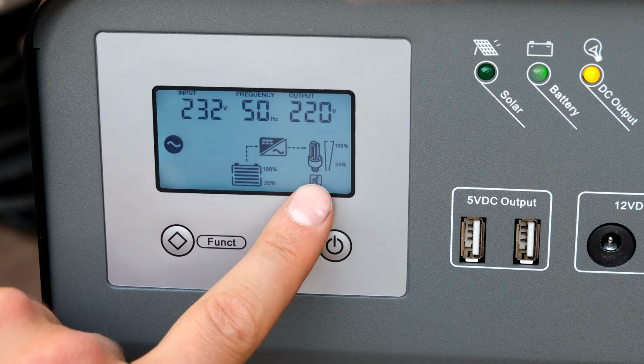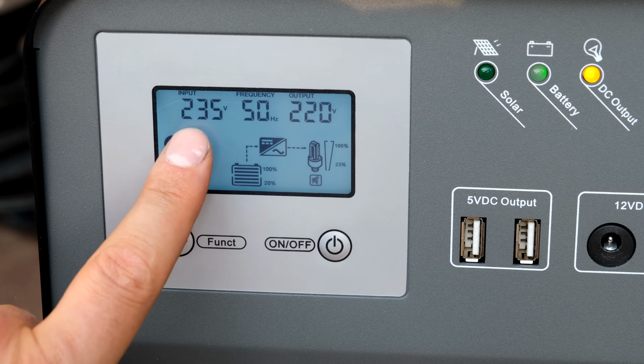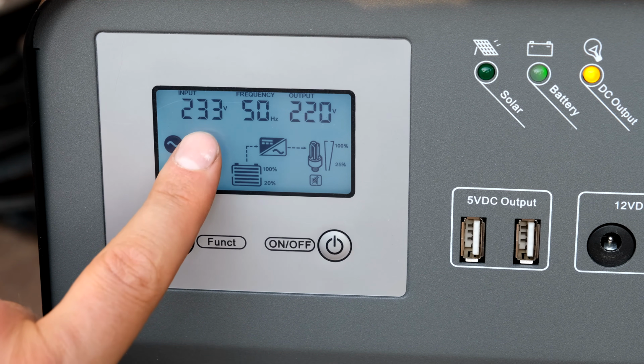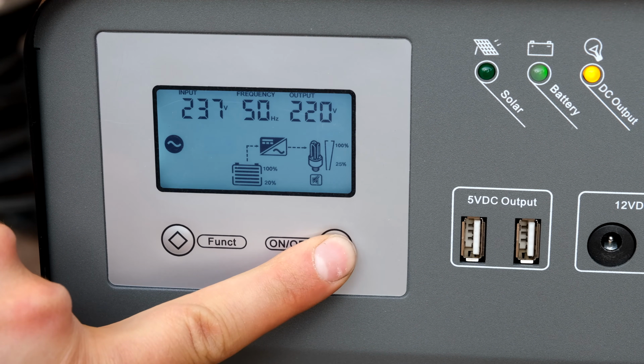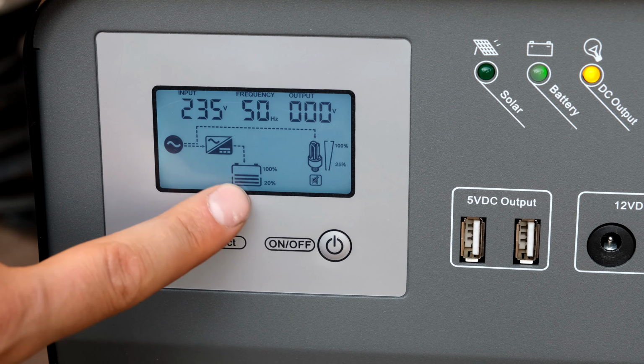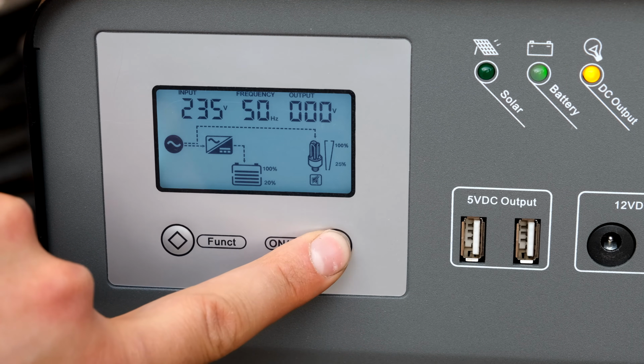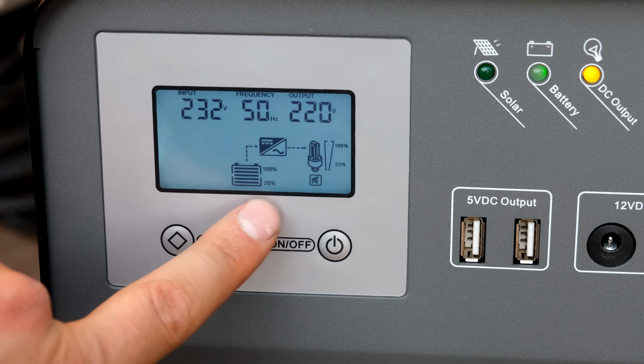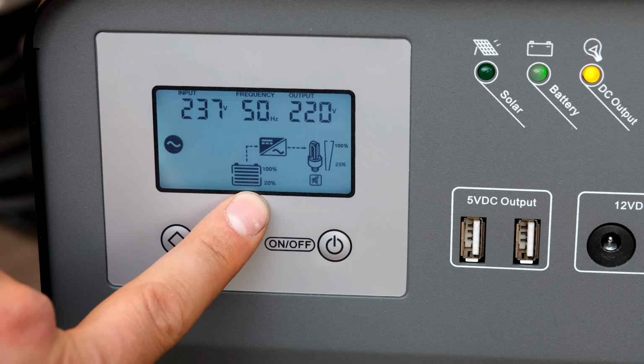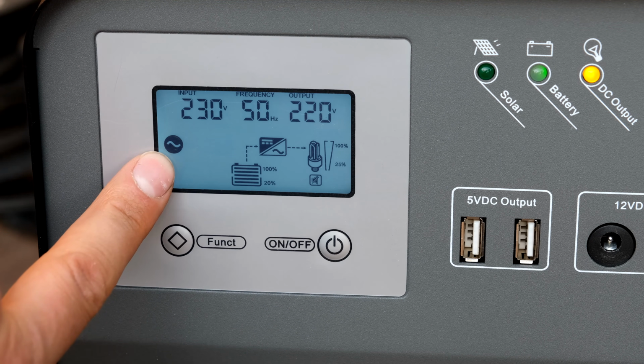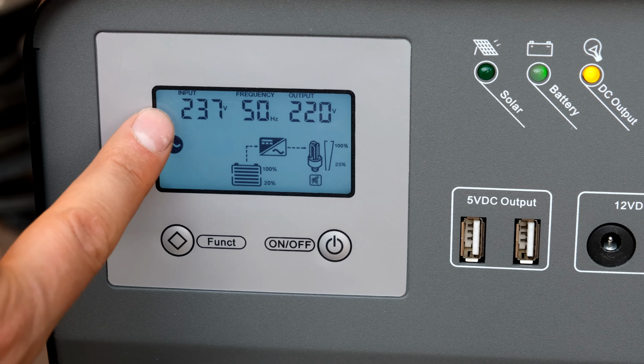Notice that the load is now being fed directly from the battery even though there is a stable input. Even if I switch the load off, it does say it's charging the battery. And now when I switch the load back on, notice that it's now fed from the battery rather than from the supply or the mains, even though there is a mains voltage here.